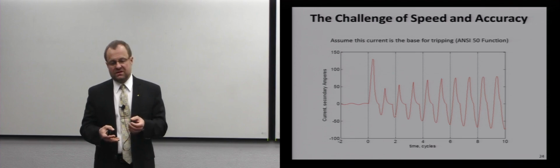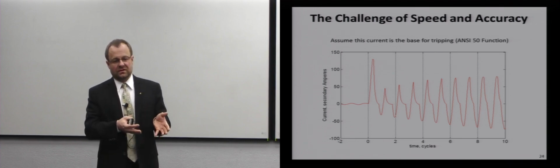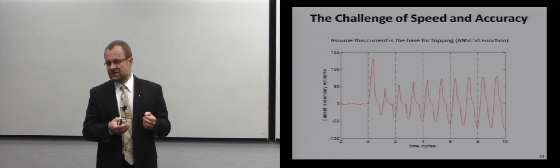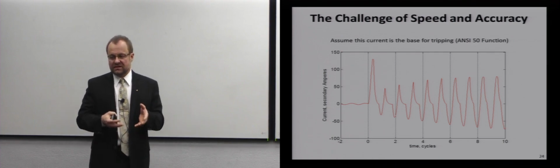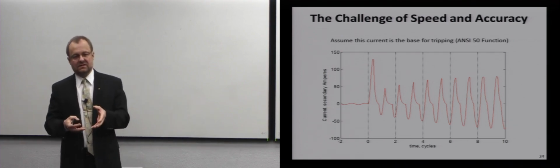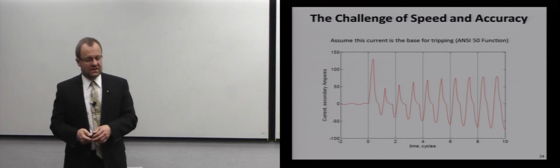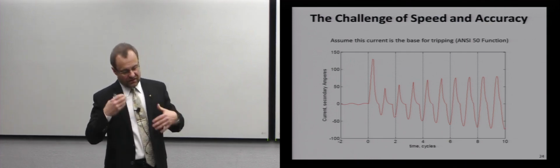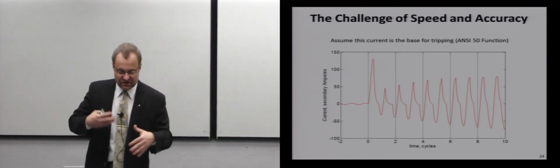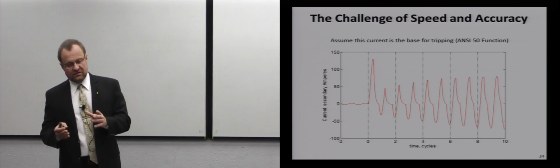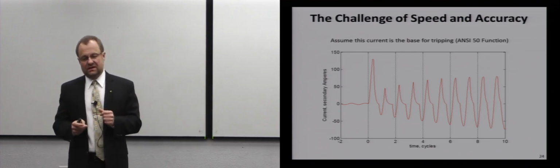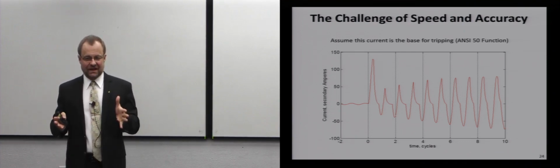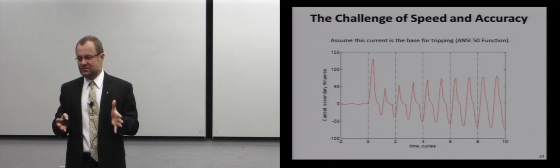Some of them run a thermal model for a motor because they are motor protection relays. Some of them provide distance functions because they are line protection relays, right? And we have our silicon to really crunch the data. We build that silicon for minimum latency. And now what do we do? How do we decide that we trip or not to trip, right?